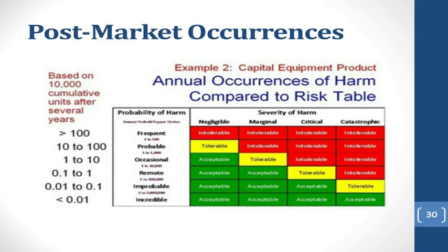And the company that made that device basically decided that any risk had to be modified or mitigated down to below a certain level, because if it was above a certain level, it was considered too high of a risk. And what the lawsuit was about was that the manufacturer said, no, we estimated the risk and we got the risk down to an acceptable level. But what the plaintiff alleged was that, no, in fact, you didn't estimate the risk properly, and it was still at way too high of a level, and that's why this terrible problem occurred.